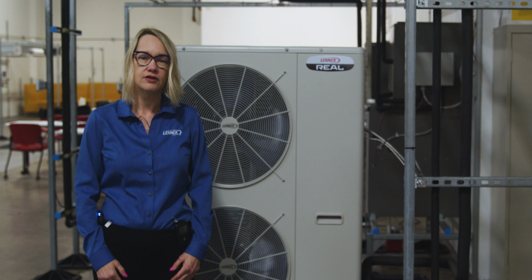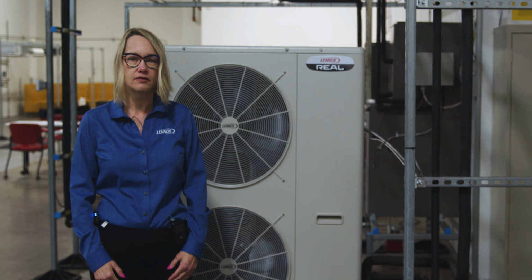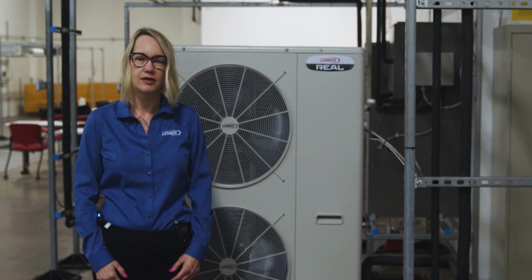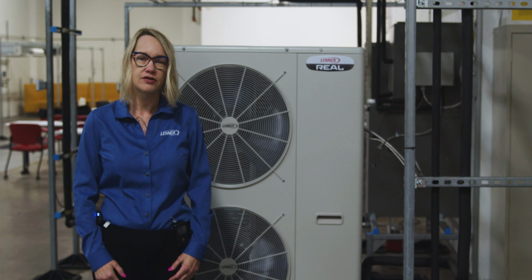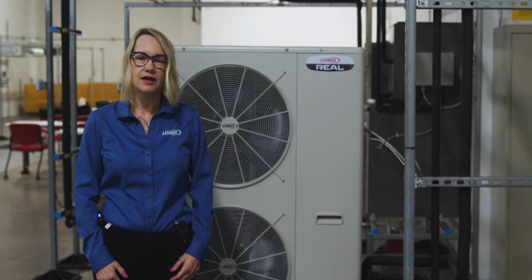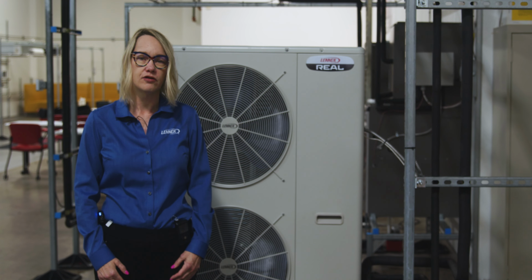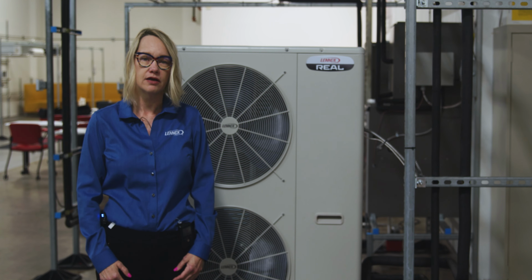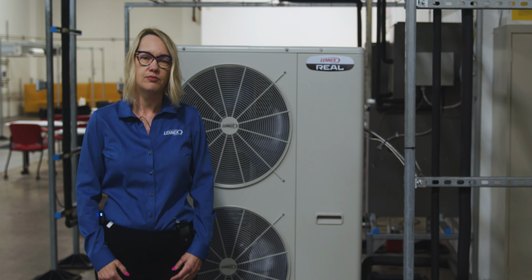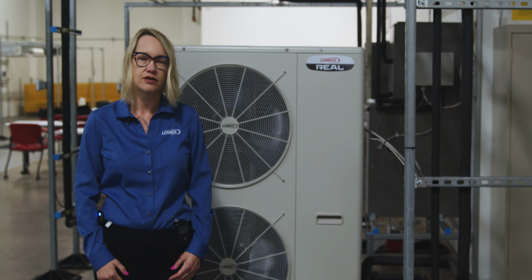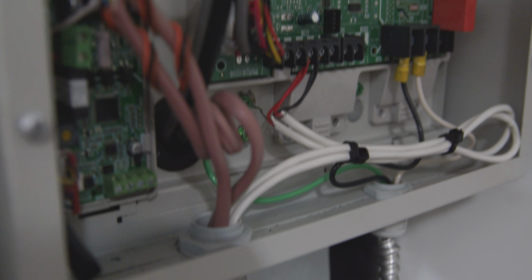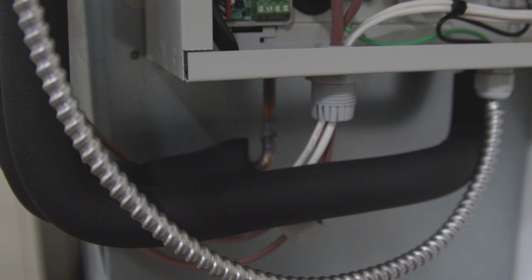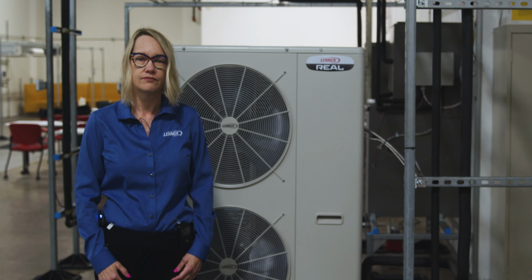The piping you're connecting to may or may not be that size. The piping size is determined by the piping length. Refer to the system's calculation and selection report for pipe sizes and lengths. The pipe connections at the indoor unit may be flared or brazed depending on the type of indoor unit. The system has one VWMB wall-mounted unit which has flared connections, and 2 AHU control kits connected to an ML296 furnace and a VHHA front return unit, all of which have brazed connections.